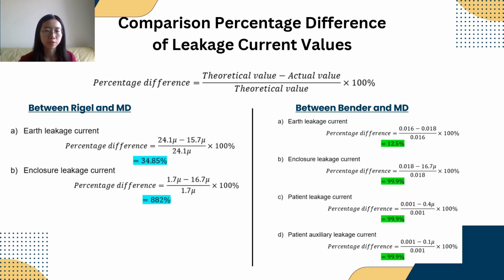Next, comparison of the percentage difference of leakage current values by using different devices. We calculated the percentage difference by using this formula: theoretical value minus actual value, divided by theoretical value, times 100%. Comparison between the reference device and the measuring device: for earth leakage current the percentage difference is 34.85%, and enclosure leakage current percentage difference is 882%. Comparison between Bender and the measuring device: for earth leakage current, the percentage difference is 12.5%, and for the following enclosure LC, patient LC, and patient auxiliary LC, all of it is 99.9%.